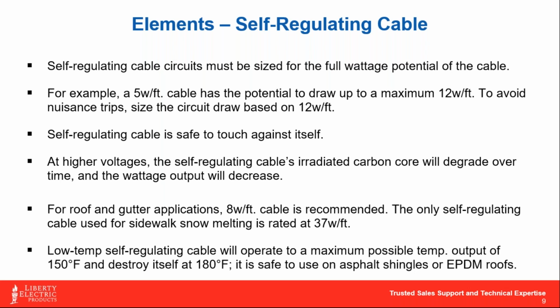The only downside is that usually the higher the voltage rating of the cable, the less life expectancy it's going to have. Okay, now let me put that in perspective as well. If you have a better grade commercial industrial cable that's got a life expectancy of around 15 to 20 years by itself, 277 volt might turn that into about, let's call it, an 11 to 14 year cable, but it's going to run really well for those years that you have it.